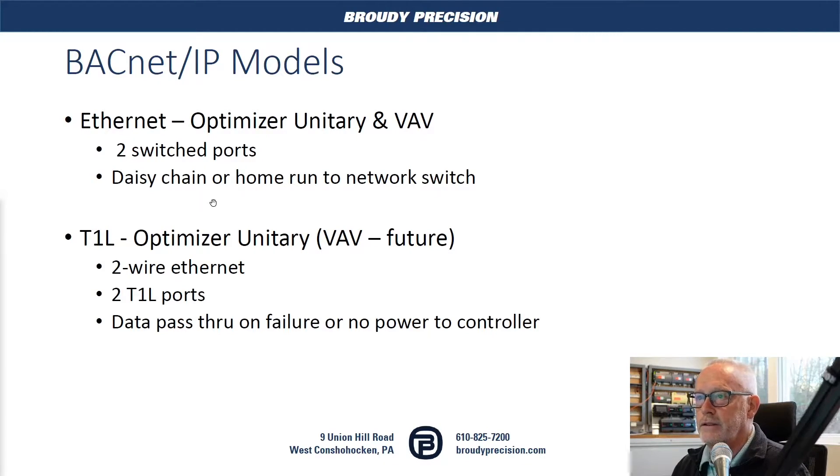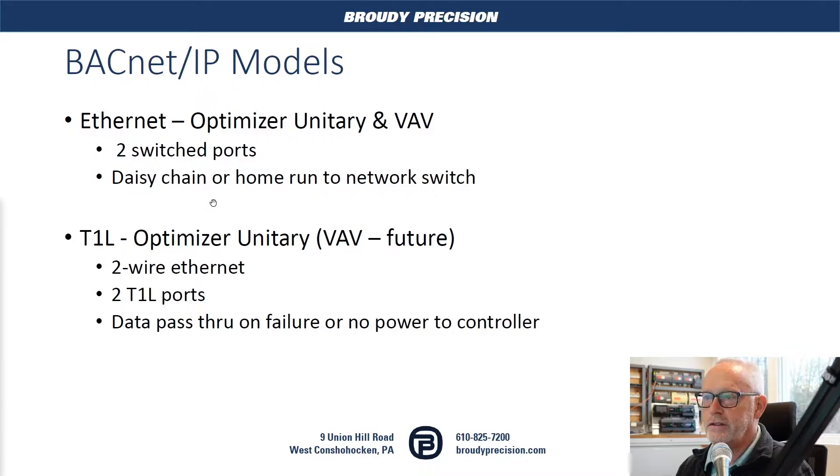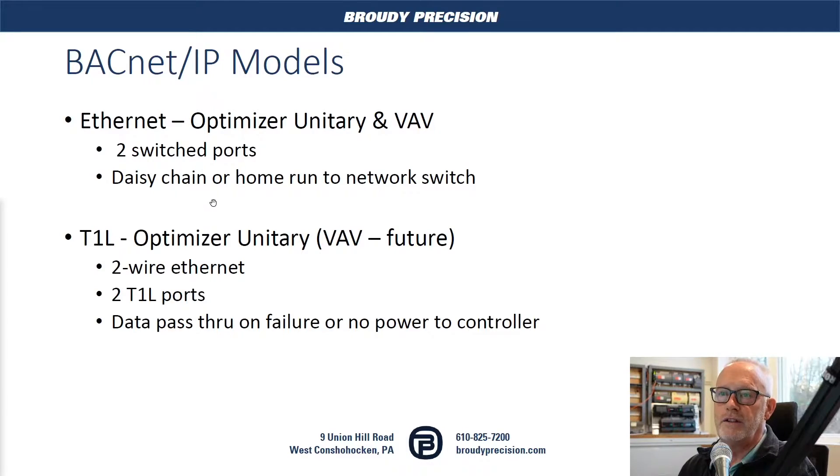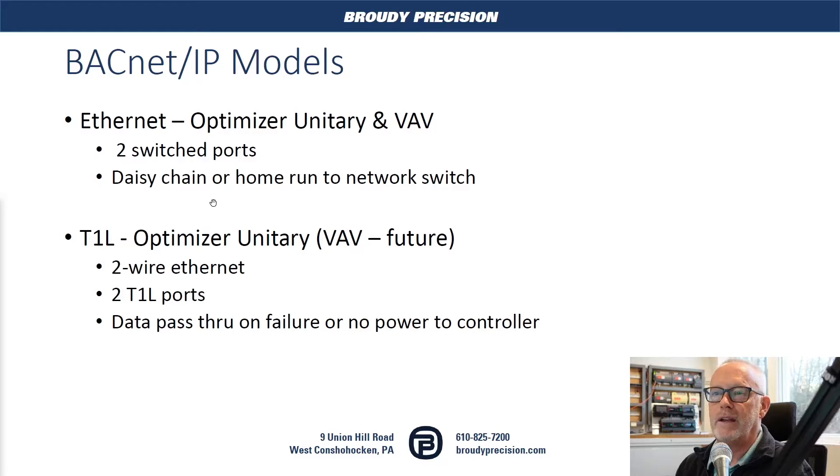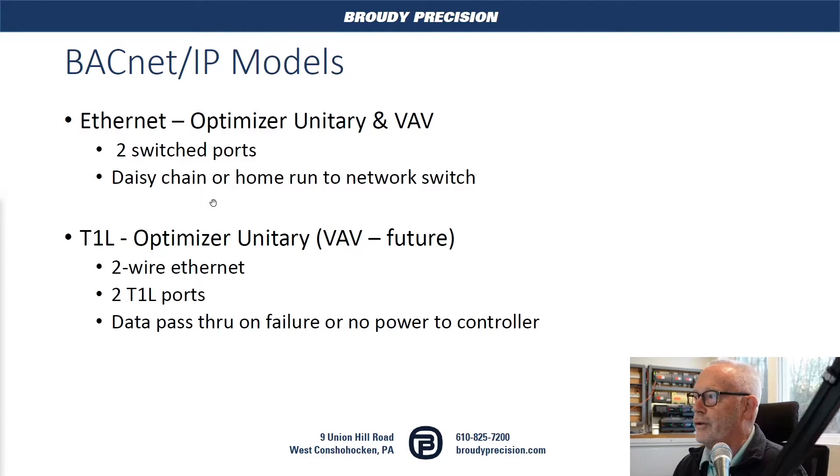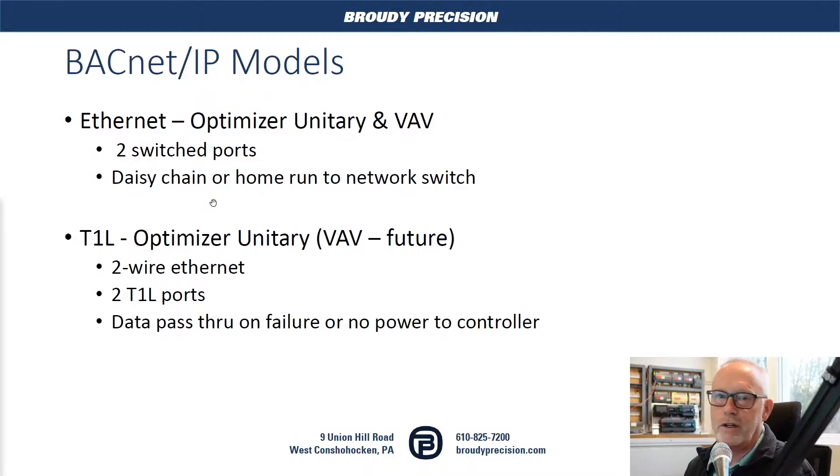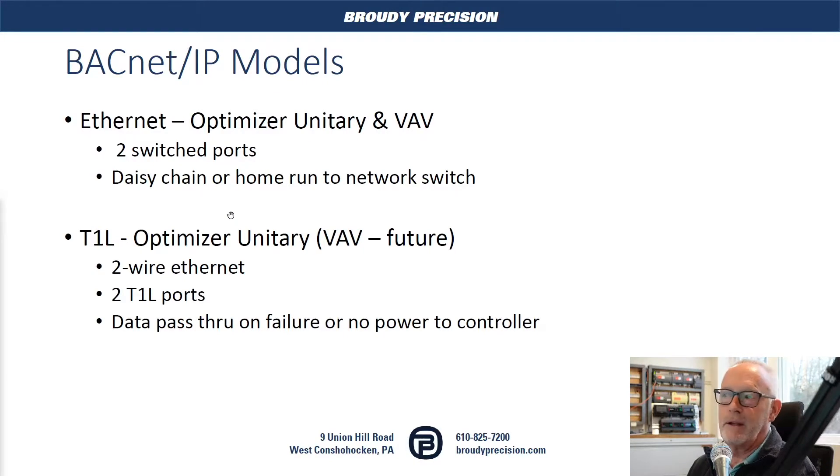Standard Ethernet, you've got roughly 300 feet between devices or between switch and devices. T1L, you have 1,000 feet, basically 300 meters between devices. So it's a very good means of communication, great way to reuse existing wire to be able to run BACnet IP.